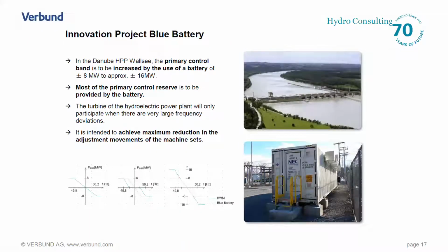Apart from the pumped storage power plants, we have some other smaller projects to add flexibility to the grid. One is the Blue Battery project, where we managed to widen the primary control band of one of our Danube River power plants by adding a battery. Most of the control service is done by the battery itself, and the contribution from the turbine comes a step later into this primary control scheme. The idea is to reduce the movements of the mechanical system of the turbines, which were originally not designed for use in primary control.